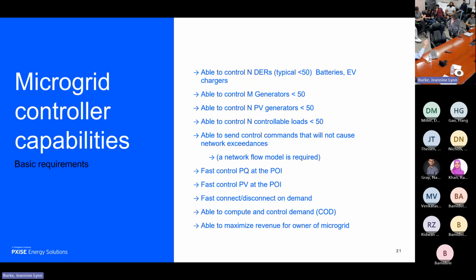We need a new generation of PLCs that don't use the 50-year-old PLC analogy of how to write software. We wrote the software one time in C, and it's driven off of a database, and it's configured. So the field engineers, they don't know what's underneath. They just know it runs at 60 hertz, and I can configure it through an Excel spreadsheet, and now my control system's working. That's in theory. It doesn't always work that way.